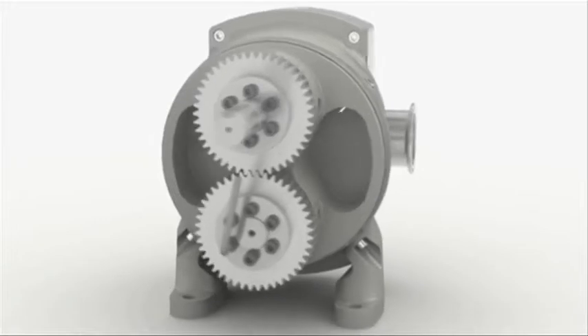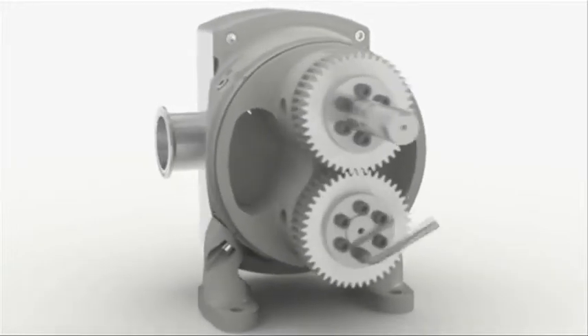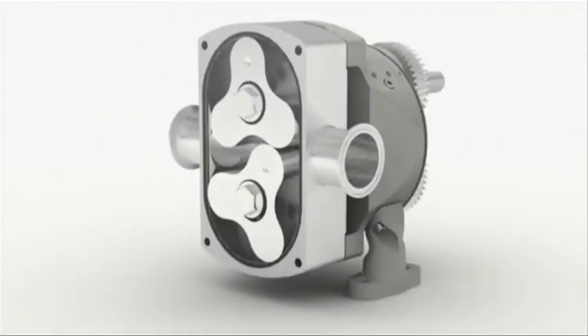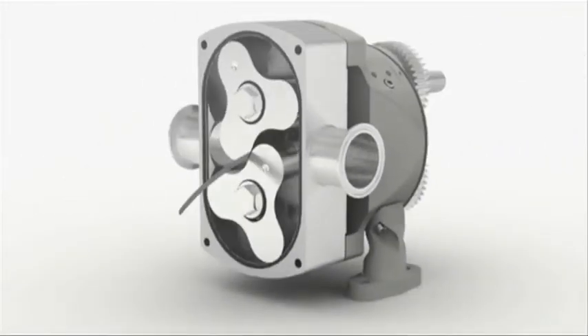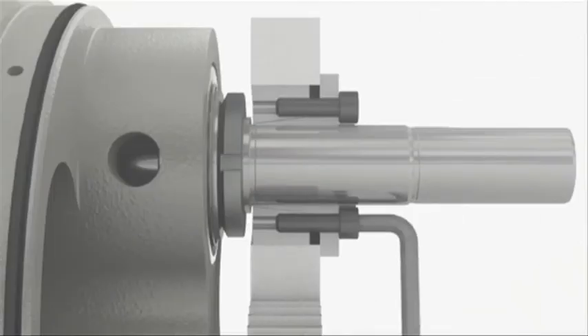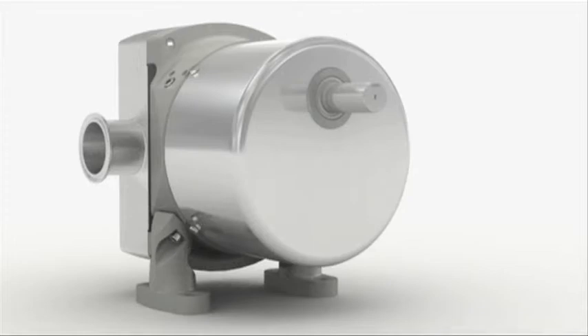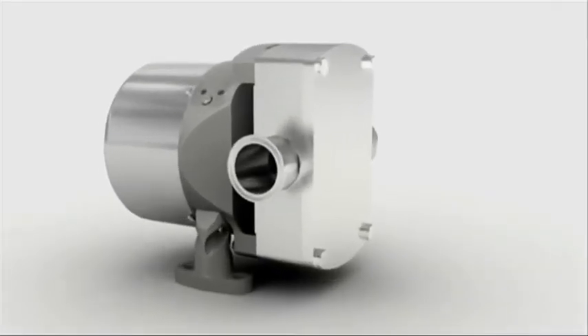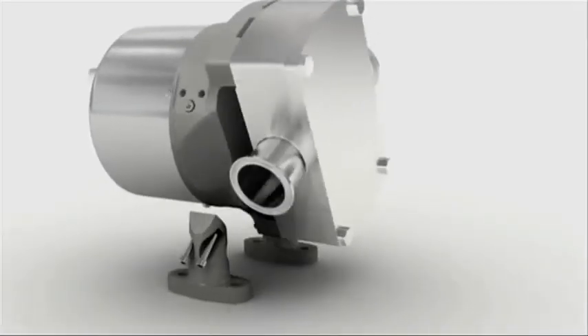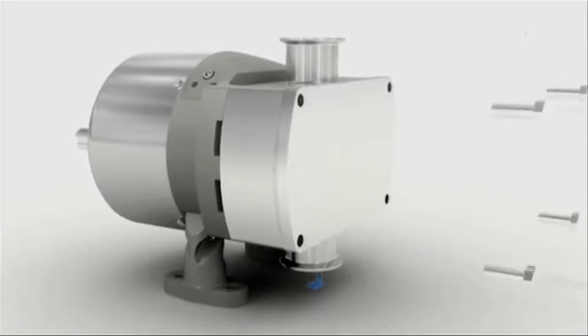The Optilobe features taper-lock timing, which highly simplifies the timing procedure and reduces maintenance costs. And with the elimination of keyways, users can benefit from increased pump life. The Optilobe range features universal mounting, which gives you complete installation flexibility throughout the plant.